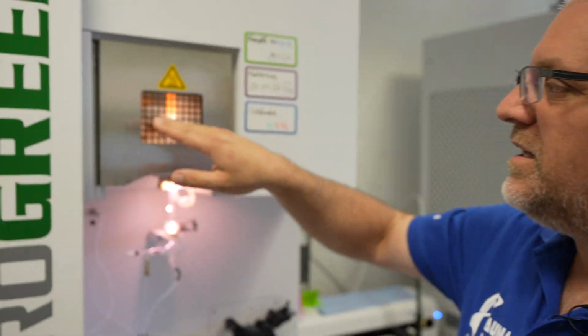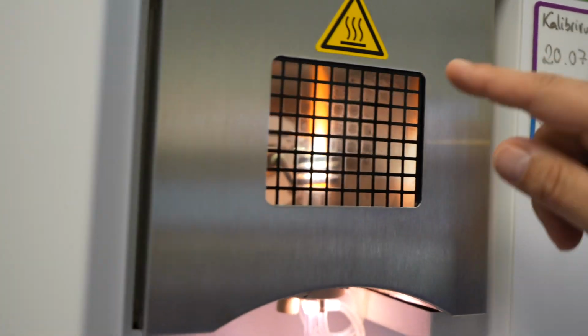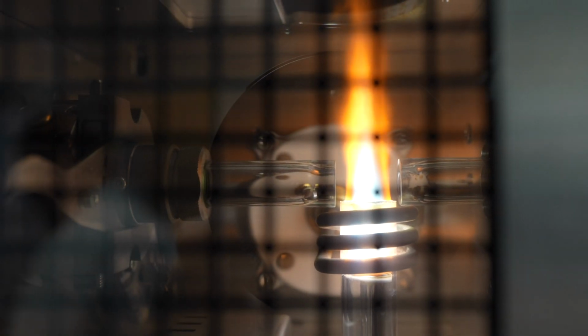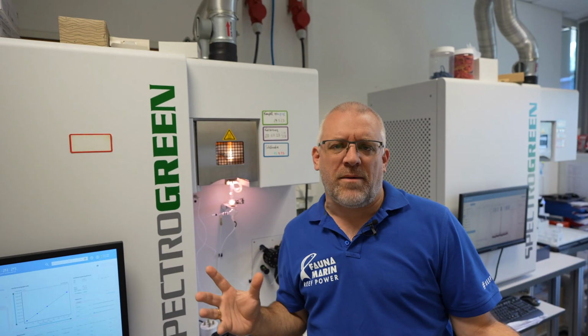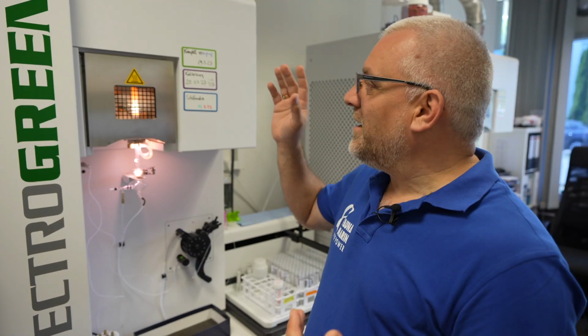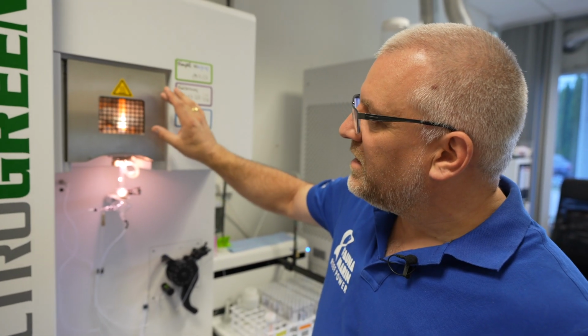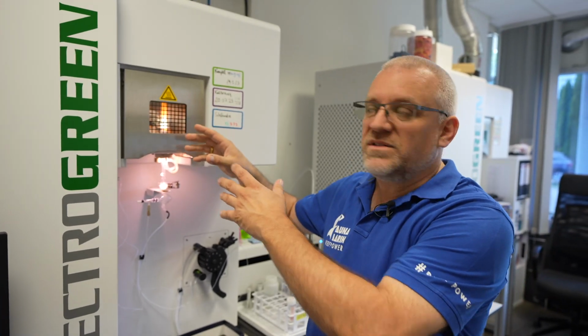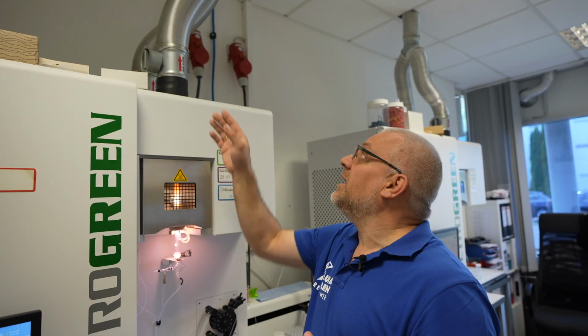At the two tubes here, you see that we have cameras looking at two sides of the flame, exactly at that part which is most stable, which doesn't give a lot of interferences. And the whole body of the machine is a huge camera system which checks the color and the amount of light. Due to the calibration and the cleaning which we do daily, sometimes twice a day, due to the high amount of tests we do, the machine knows, oh, I find this color in red and this amount, and that means I have a sample with 8 milligrams of strontium in the probe. After the salt water is nebulized and burnt here, all the salt and all the dirt which results from this test goes out and is released with the airflow system.